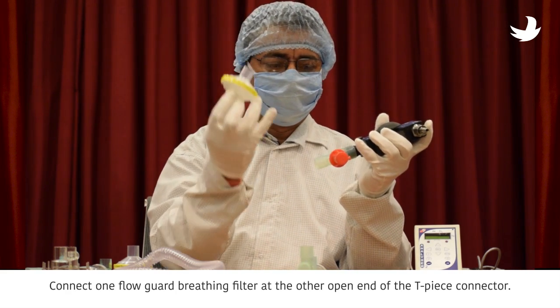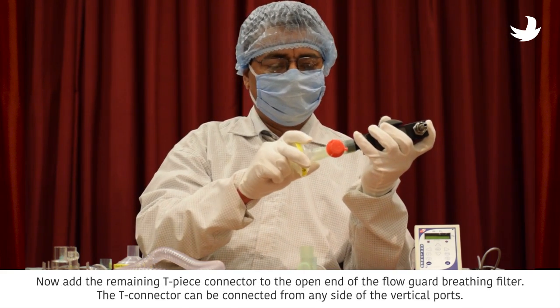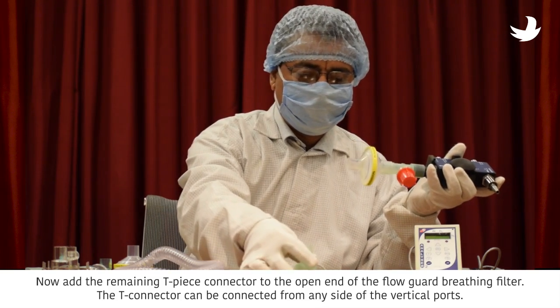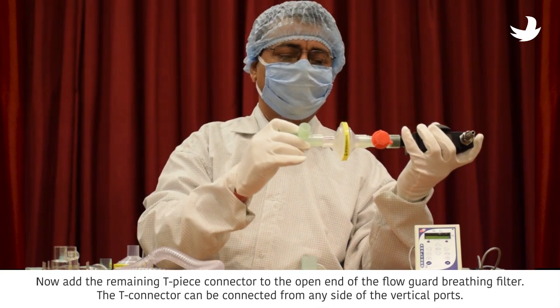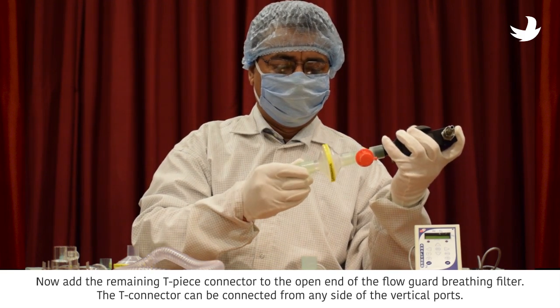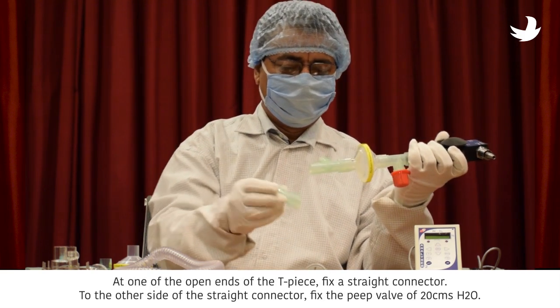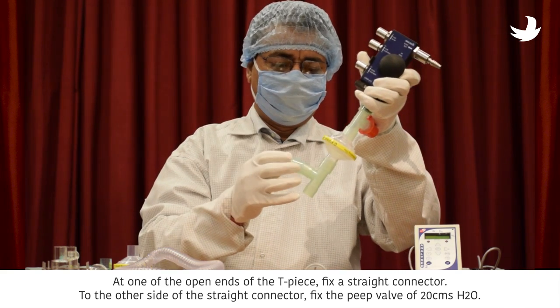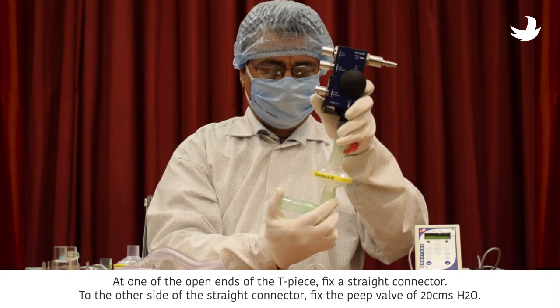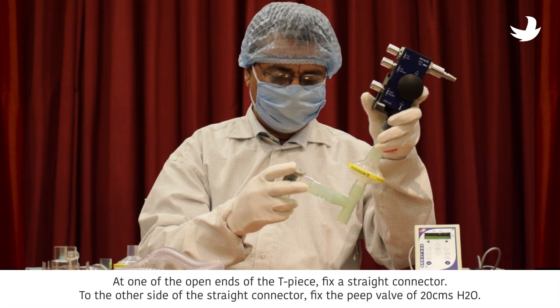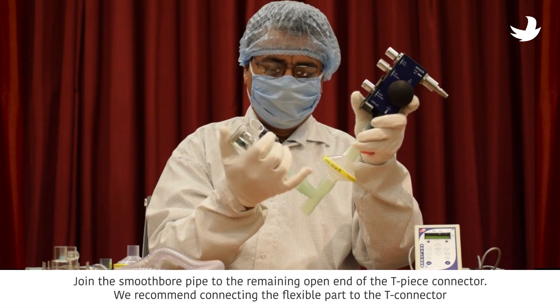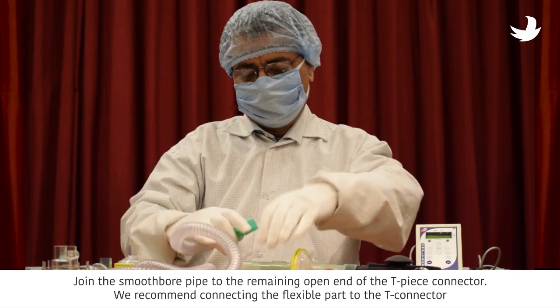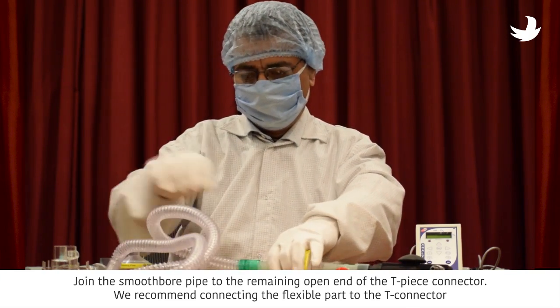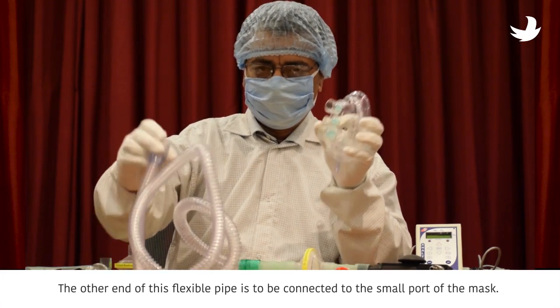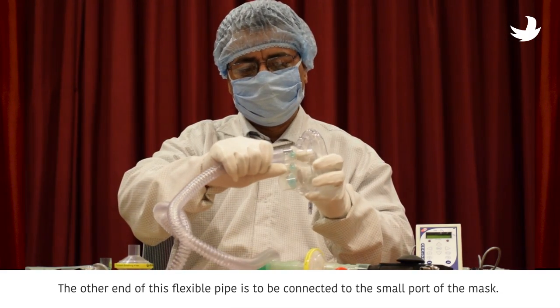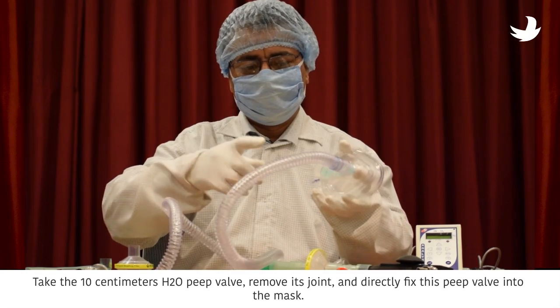Connect one flow guard breathing filter at the other open end of the T-piece connector. Now add the remaining T-piece connector to the open end of the flow guard breathing filter. The T connector can be connected from any side of the vertical ports. At one of the open ends of the T-piece, fix a straight connector. To the other side of the straight connector, fix the PEEP valve of 20 cm H2O. Join the smoothbore pipe to the remaining open end of the T-piece connector. We recommend connecting the flexible part to the T connector. The other end of the flexible pipe is to be connected to the small port of the mask.